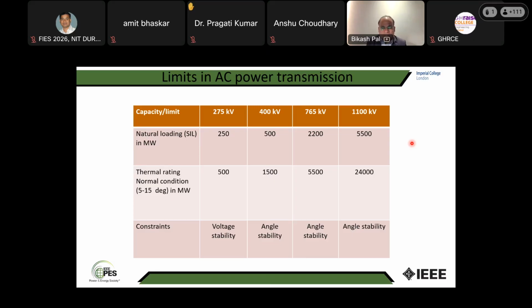Now, because this capacitance is charged with the transmission voltage of say 400 by root 3, there would be omega C V square, that reactive power, generated. And because the line also is carrying current I, and if XL is the inductive reactance, that line also would be absorbing I square XL amount of reactive power. So if we fix the length, say per kilometer, I square XL is equal to omega C V square. So the line itself is generating a capacitive var, which is being absorbed exactly by the inductive circuit element in this transmission line. So that means there is no net var generation or absorption.